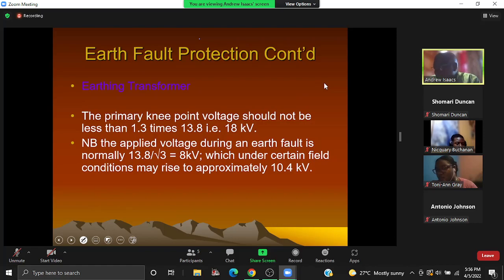Now, you are aware that you have your earth fault, and you would have seen this whether we were doing the calculations or in your labs. You would have seen that the system voltage falls under fault. So I'm telling you that it may fall in the region of 13.8 over root 3, which gives us 8 kilovolts. And the field conditions we are talking about here is that same 1.3 multiplier that we are using. So the 8 times the 1.3 gives you the 10.4 kilovolts.